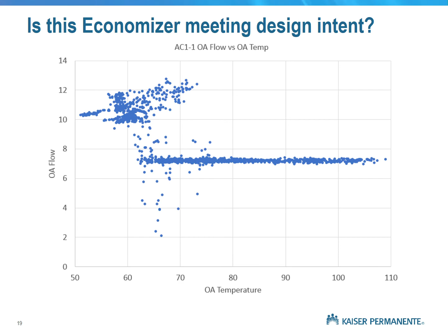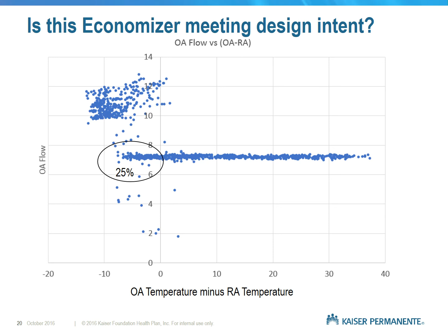Actually do that too, right? So here's a plot, and we simply shifted the x-axis to outside air temperature minus return air temperature. And anytime outside air is less than return air, that produces a negative number, so the economizer should be open. Now it's probably okay if 5% or 10% of those points are in the cluster where it's not open. 90% of the time the economizer would be open. But in this case, that cluster of points is 25% of the interval data. And I'm not sure that's right. I don't think that should be accepted.